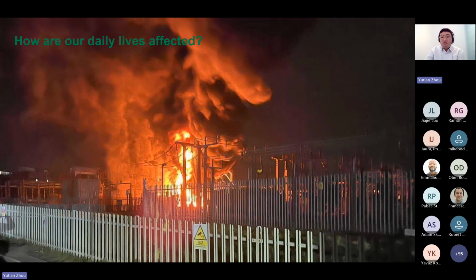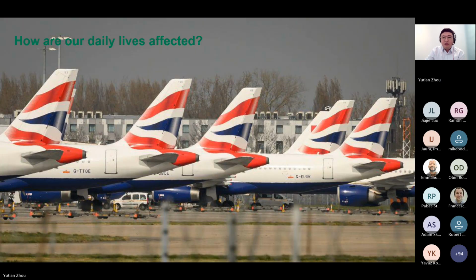Airport. Using forensic analysis from both National Grid Electricity Transmission and London Fire Brigade, this review has seen evidence that a catastrophic failure on one of the supergrid transformer's high voltage bushings caused the fire to ignite on the supergrid transformer. This was most likely caused by moisture entering the bushing, causing a short circuit. The electricity likely then arced, which combined with air and heat to ignite the oil, resulting in the fire.